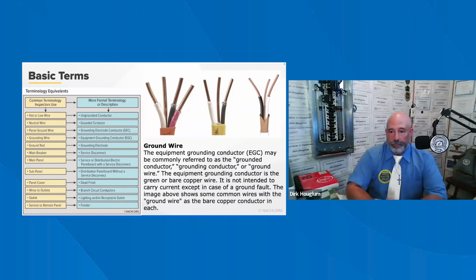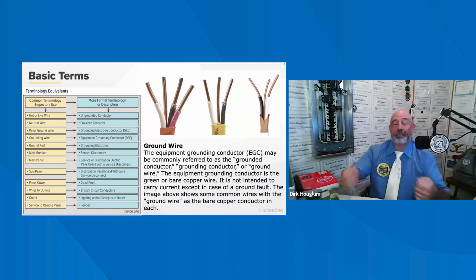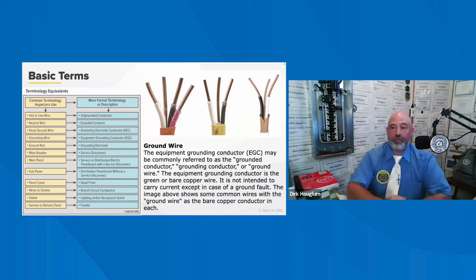Okay. Current, a measure of the rate of flow of electricity through the conductors. Current is measured in amps, and we're going to talk about that. The dead front cover, I also like to call that your blast shield because if you're taking off that cabinet, you want to kind of hold that up just in case something does explode out of there. You don't want something running out at you either. I've had a rat run out at me once.